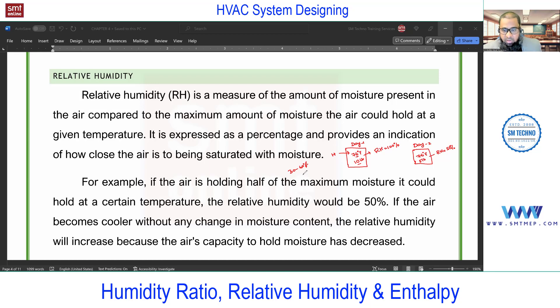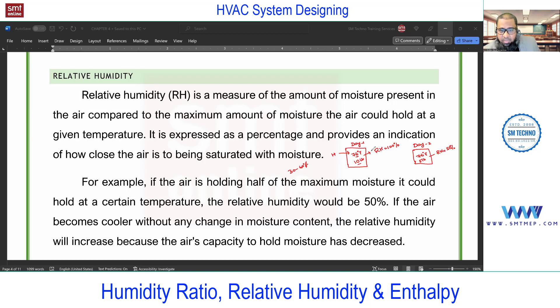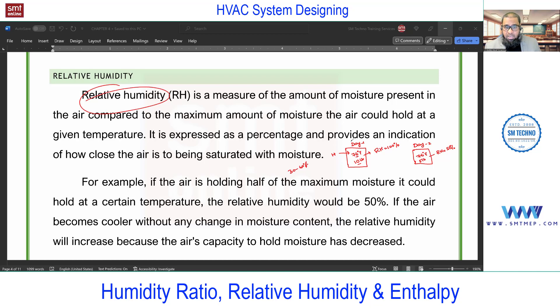For room comfort, the humidity level should be 30 to 60 percent. Below 30%, you feel dryness of skin; above 60%, you feel sweat, stickiness, and a muggy condition. In both cases it is not comfortable. So whatever the maximum possible moisture is at that particular temperature, maintaining 30 to 60 percent of that gives comfort with respect to moisture.